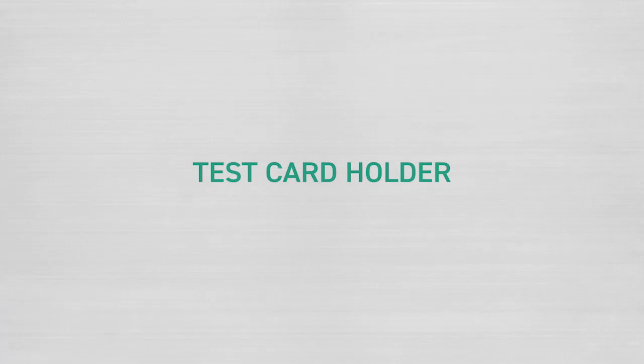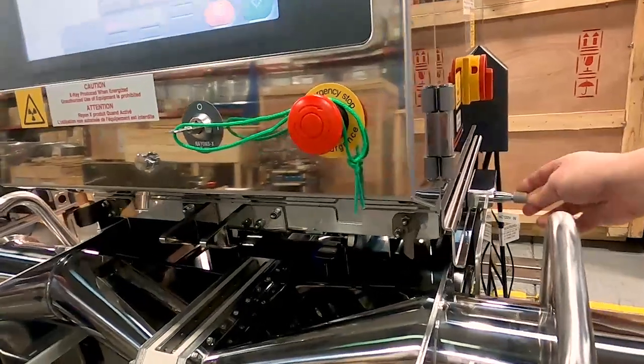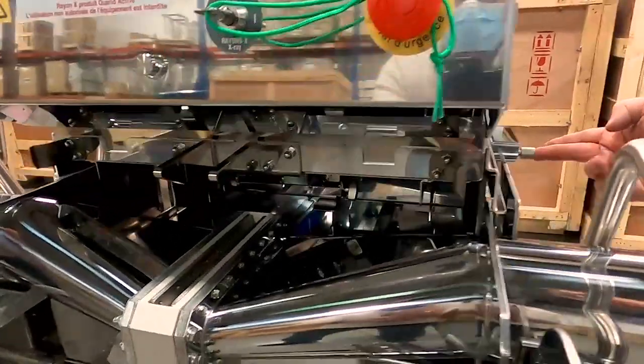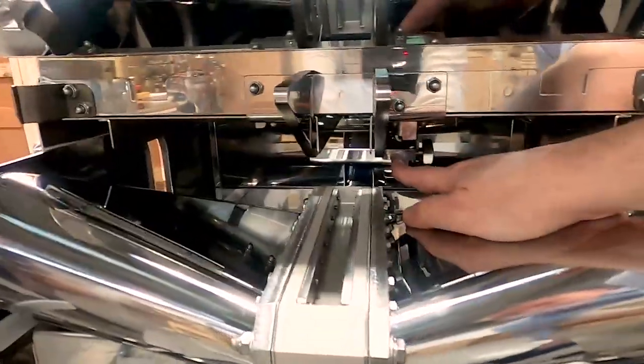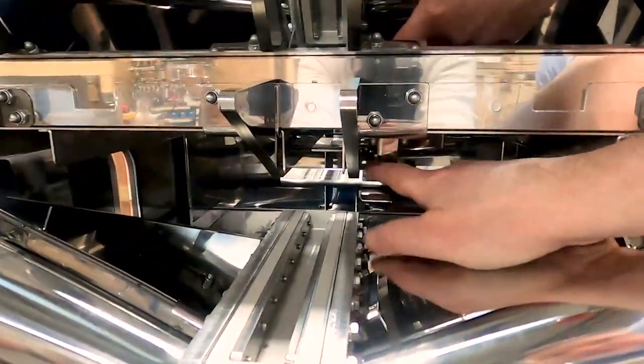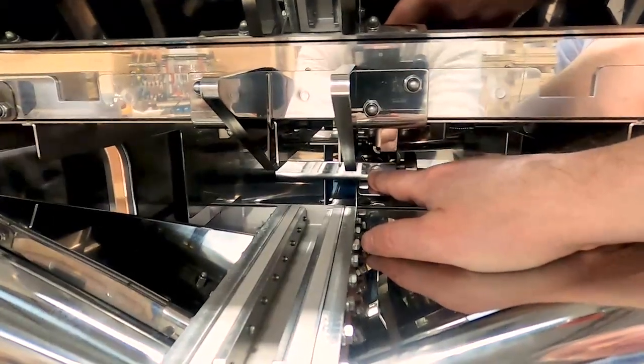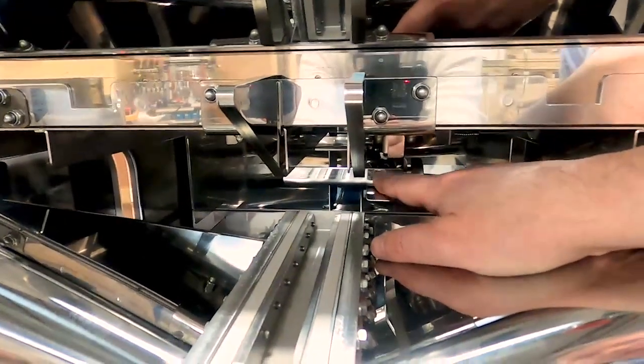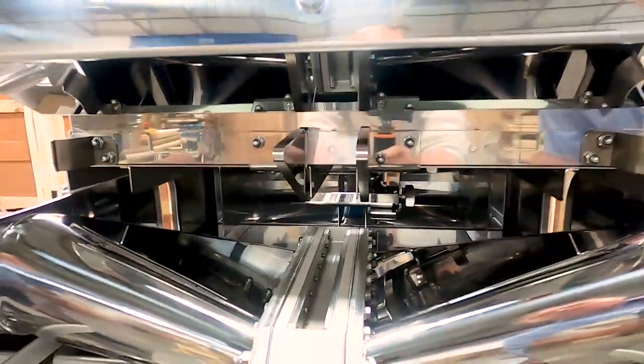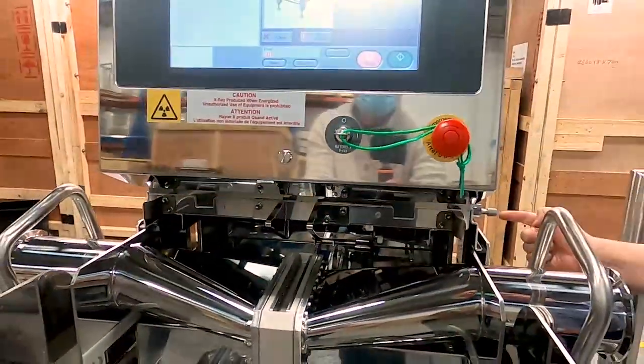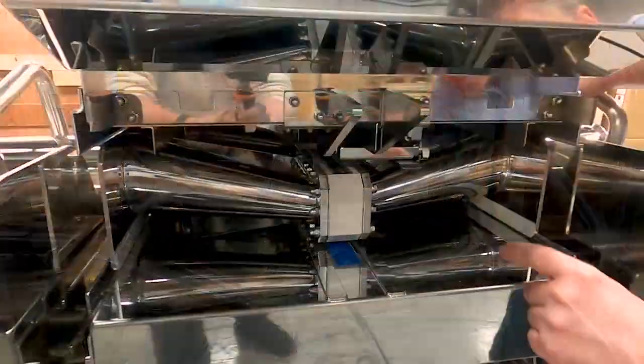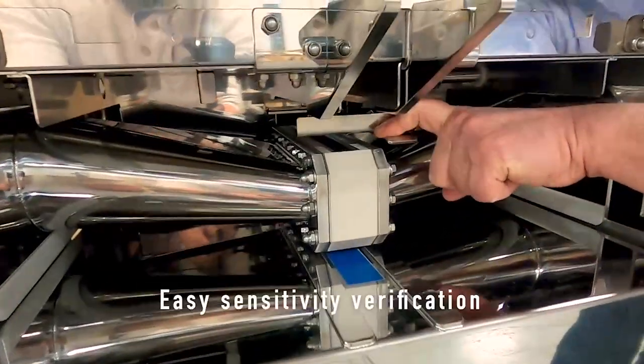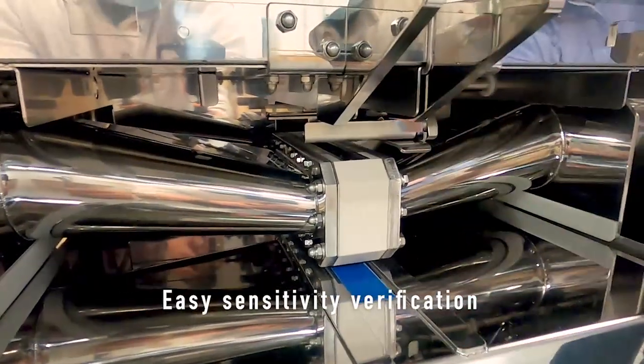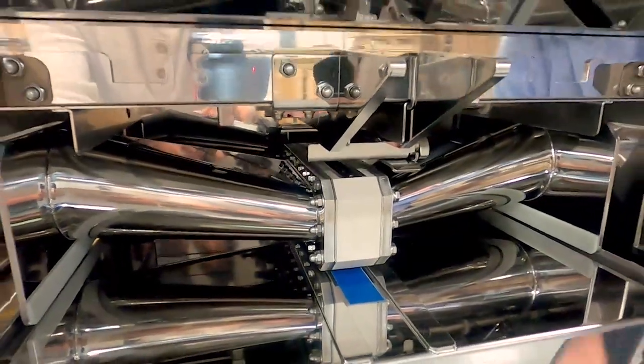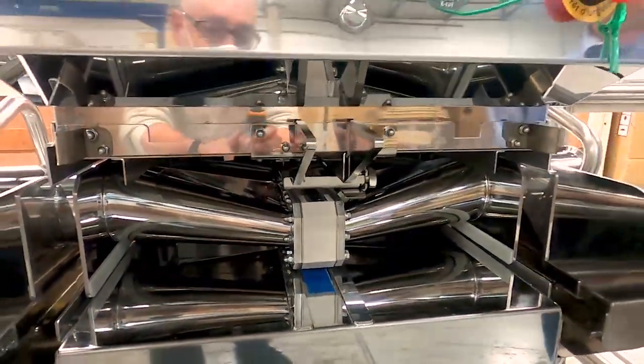One nice feature for calibration and testing is this test card holder. So what we'll see here is if I push this plunger in, this little holder pulls out. And what you do is you put your test card in there. So I could have, say, a small piece of metal and a piece of synthetic quartz to simulate bone. And I could leave it in this test card holder. And when quality wants to do a test, they simply need to pull this out or push this in. So what it'll do is it'll put the test card right over the inspection manifold. And now it'll be in the image, and it'll make sure that you're detecting whatever contaminants you have on the card. And then you can verify that it's rejected through the ball valve reject. And it's as simple as that.